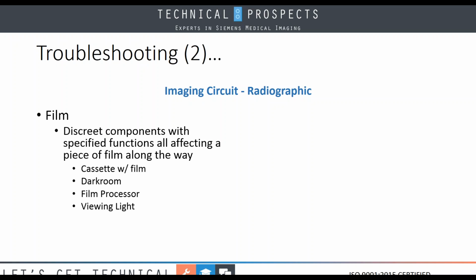And that's supposed to be within a specified range. If you have an image quality issue, the first thing I would do is run a film through that film processor and see if our processing has changed and is now outside the QC range. If it is, my problem's in the processor. It's not in my imaging chain, not in the other part of the imaging chain.